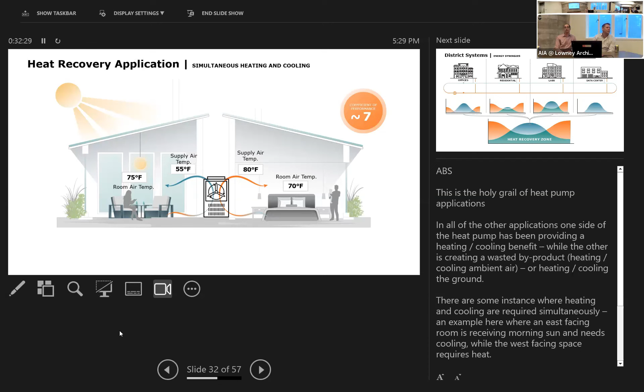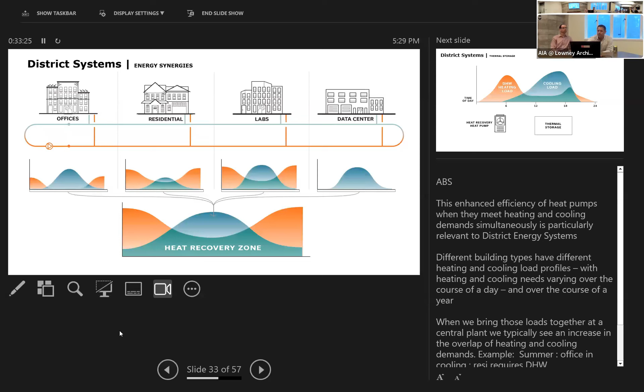Now, at the individual building level, sometimes you'll only have a very small amount of that simultaneous heating and cooling time. But what we find is if you start looking at mixed-use developments where you've got different types of buildings, you might have an office, residential, lab building, data center, and you bring all of the heating and cooling loads back to a central plant, because it maximizes that potential to have that simultaneous heating and cooling demand. A classic example is where your office building will need cooling. At the same time, your residential and, if you've got retail, restaurants, need a ton of domestic hot water. So you bring those loads together and then you meet both of those loads with that super efficient heat recovery heat pump.